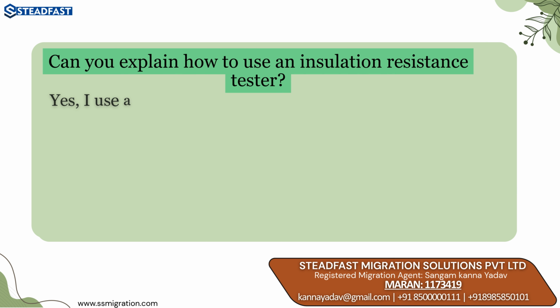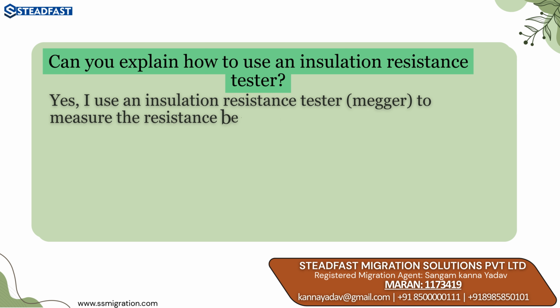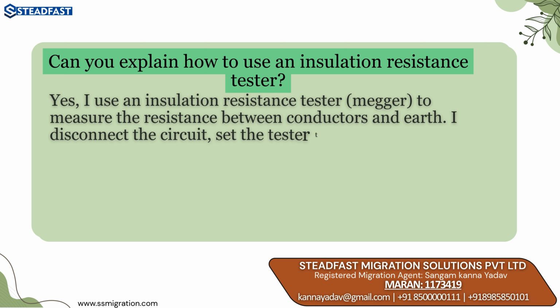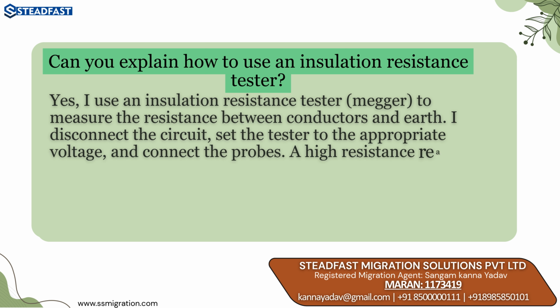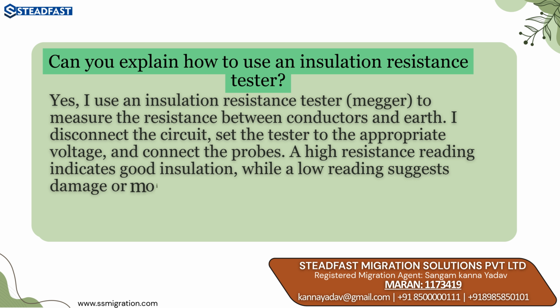Yes, I use an insulation resistance tester, a Megger, to measure the resistance between conductors and earth. I disconnect the circuit, set the tester to the appropriate voltage, and connect the probes. A high resistance reading indicates good insulation, while a low reading suggests damage or moisture.